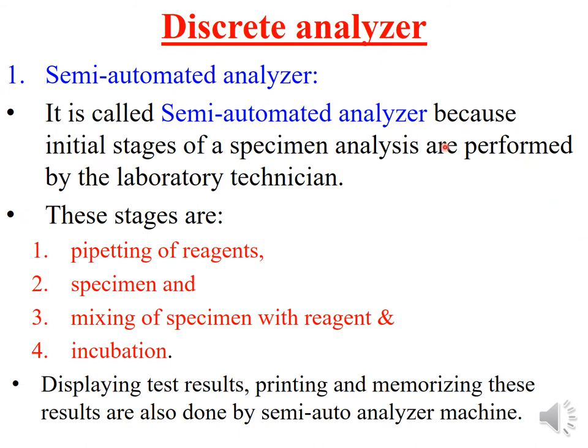Discrete analyzers are further classified as semi-automated analyzers. They are called semi-automated because the initial stages of specimen analysis are performed by the laboratory technician — some parts are done manually and the remaining parts by the equipment.